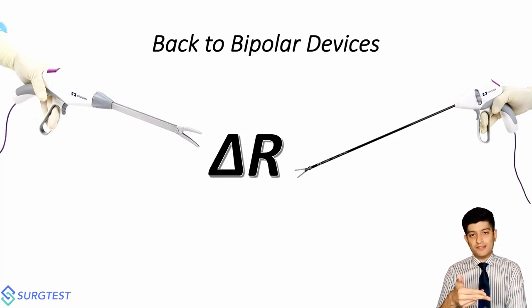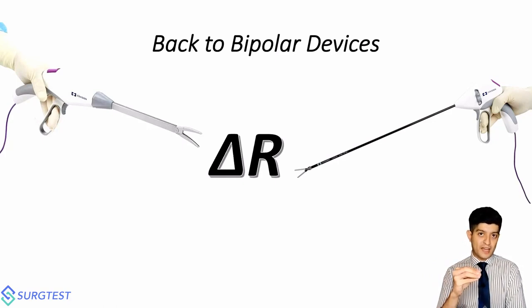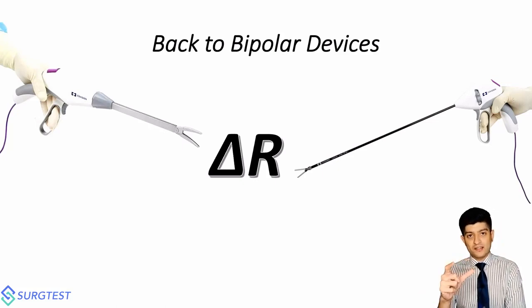When you catch tissues within these devices and you press the firing button, in a split second it sends a small current across the system and gauges the total resistance of the tissues that you have grasped. It stores it in its memory. Within the electrosurgical units, there are predefined algorithms that determine how much of a resistance change is meant to occur for vessels to get sealed within the tissue. Remember, when you're denaturing proteins within a surgical field, they become poor conductors of electricity, which means the resistance increases. So when you're effectively sealing vessels, the resistance of whatever tissues you've grasped should increase. These devices will constantly keep checking the resistance to the flow of electricity within the tissues, and when this change in resistance reaches a preset value, they stop firing current.